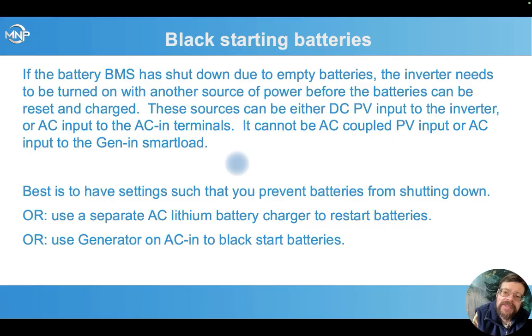Talking a bit about black starting batteries. This is when the battery BMS has shut down due to the empty batteries. This is not when the inverter has shut down due to hitting that low state of charge setting on the inverter. That will shut off the AC output of the inverter, but its brain will still be on. It'll show stuff on its screen. If the battery gets low enough, it'll actually shut down its output and the inverter will go completely black. So we need essentially, in that case, a way of recharging that battery, but our inverter won't turn on because it can't get power from the battery to turn its brain on.